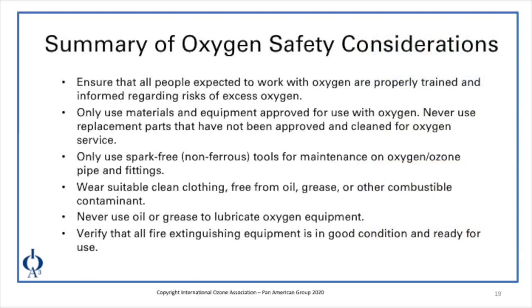For a summary of oxygen safety considerations: ensure all people expected to work on the facility with oxygen are properly trained and informed regarding risks of excess oxygen. Only use materials and equipment approved for use with oxygen. Never use replacement parts that have not been approved and cleaned for oxygen service. Only use spark-free, non-ferrous tools for maintenance on oxygen and ozone pipe and fittings. Wear suitable, clean clothing free from oil, grease, or other combustible contaminants. Never use oil or grease to lubricate oxygen equipment. Verify that all fire extinguishing equipment is in good condition and ready for use.